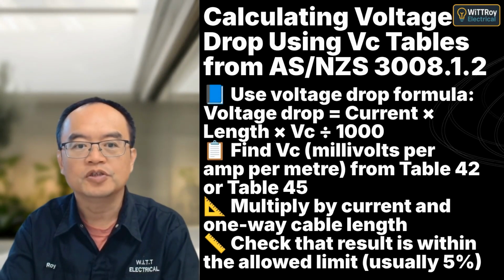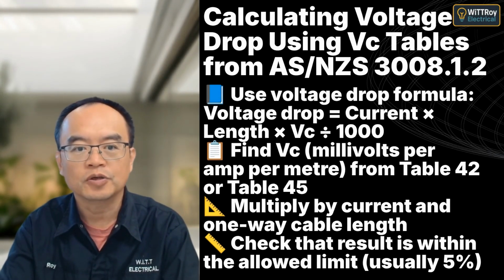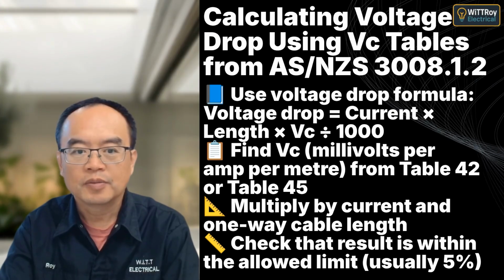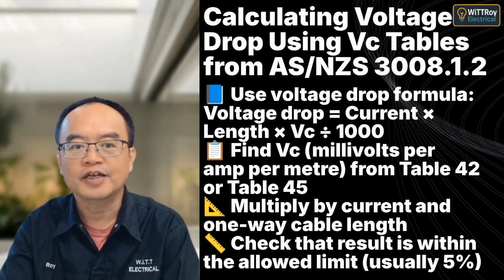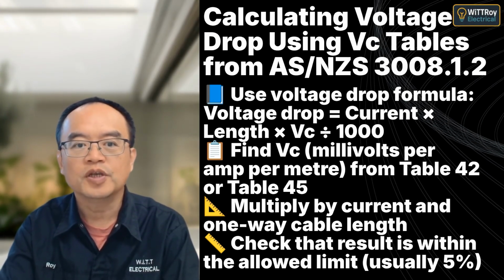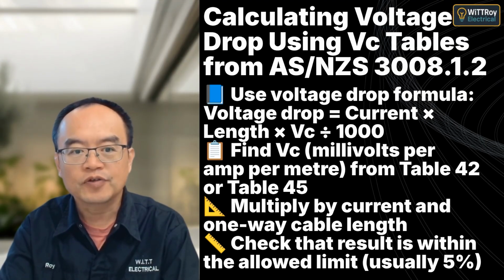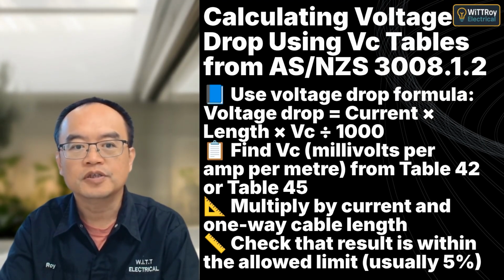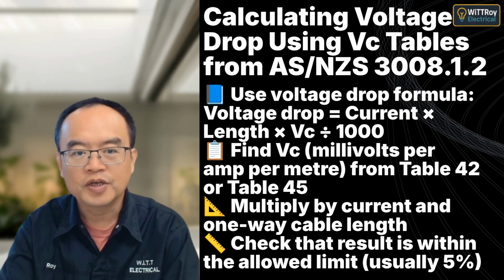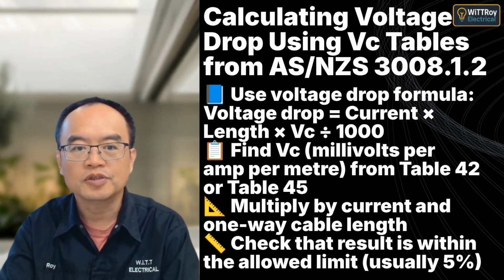To calculate voltage drop using the VC method, multiply the current by the length of the run and the VC value from AS/NZS 3008, 1.2, table 42 or 45. Divide the result by 1000 to get volts. VC is the voltage drop per amp per meter. Always make sure the final result is below the maximum limit, which is usually 5%.